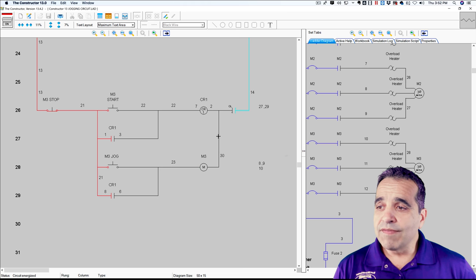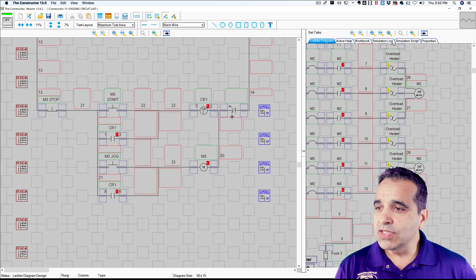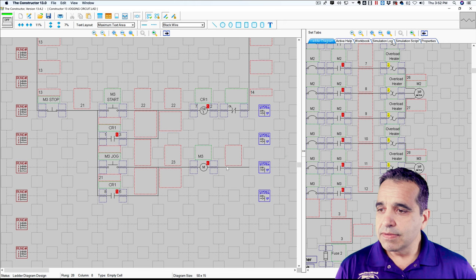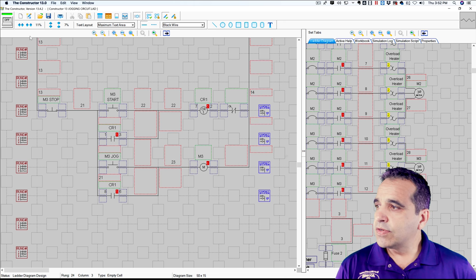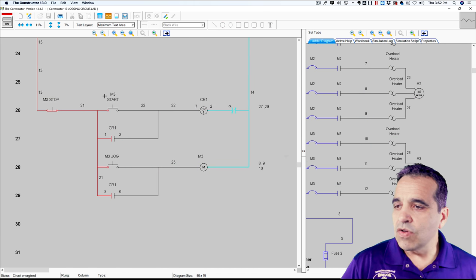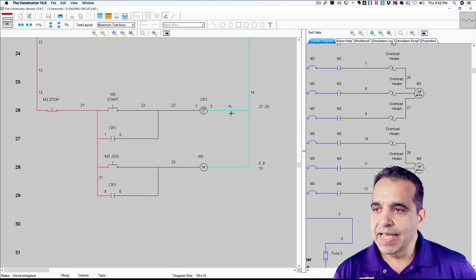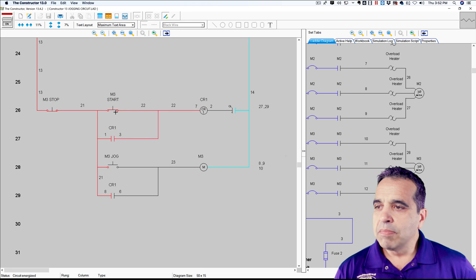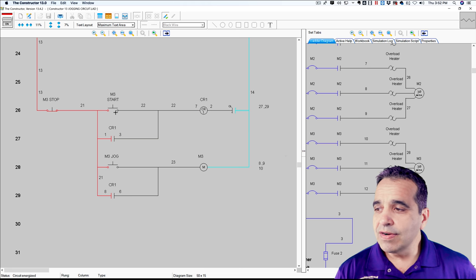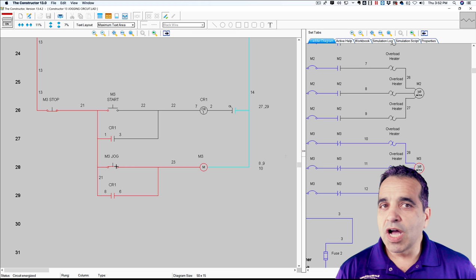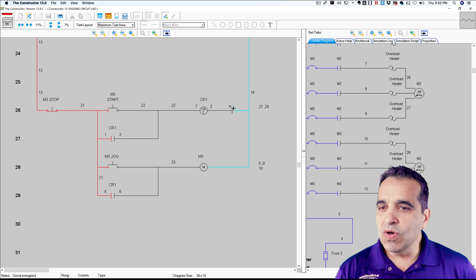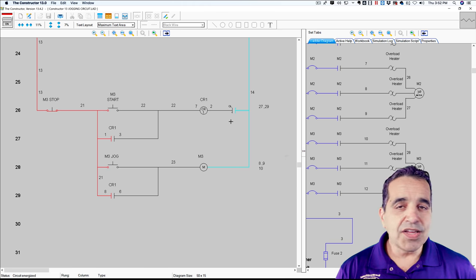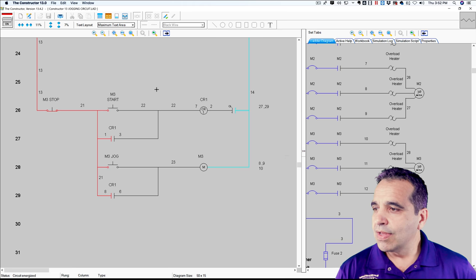But if I had wired this the other way, and let me just show you, let me eliminate that wire, eliminate that wire and turn this circuit back on. So if I had wired like this and I lost my overload, my ice cube relay won't start, but I'm able to jog my motor. I'm able to jog my motor even though the overloads are open. Not a good thing. Not good at all.